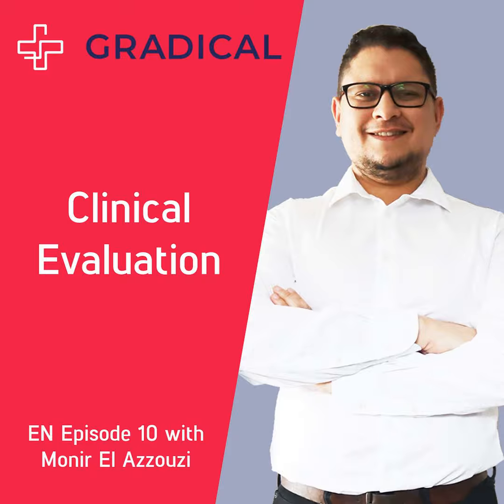And more importantly, nobody will check, if I can say, because class 1 is called self-certified, which means that you have to do the exercise as written in the EU MDR, but nobody will check. The only way they can check is if there is an issue on the market, then they can come and verify what you have done and if there is really an issue with your products. But otherwise, there is no notified body.